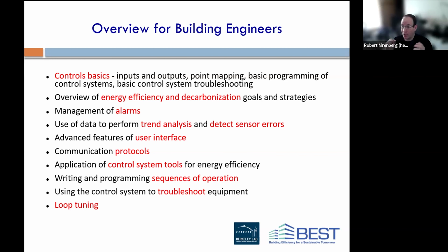And finally, one of our last topics we'll cover for building operators or engineers is loop tuning. Anytime we have an analog control signal, something that's a percentage instead of just an on-off value, things like fan speeds, outside air dampers, or valves, these are common. Behind those controls, we have what's called a loop. And if you've ever seen a device that just bounces up and down constantly, never settling to an even keel, that's often a loop tuning problem.